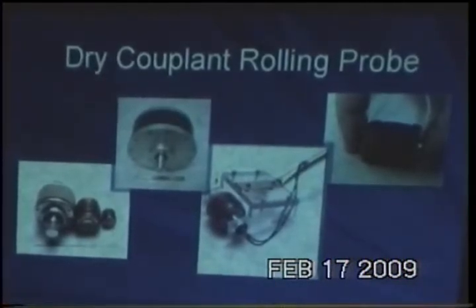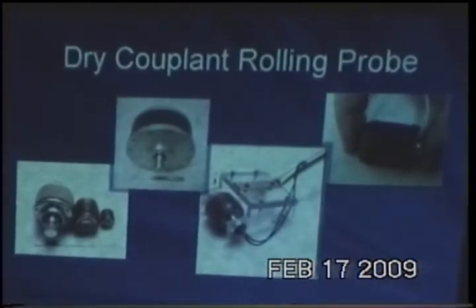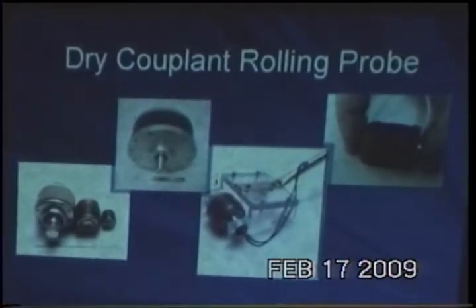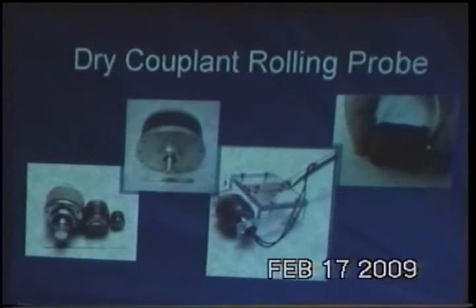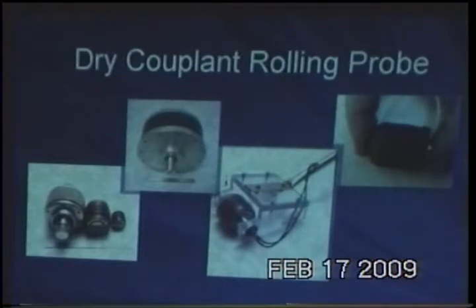The other ones you see here are our standard transducers for non-destructive testing. The set of three there is a 5-inch, a 2-inch, and a 1-inch diameter. The 1-inch one pictured is for thickness measurement—pretty small, you don't think about it when you say an inch diameter, but there's Larry's thumb and finger just holding the edges of that thing. The rolling probe is just a fancy housing; any transducer can go in it—angle beam, dual focus, L-wave, shear wave, thickness mode.